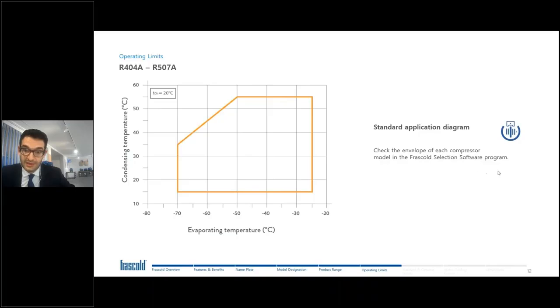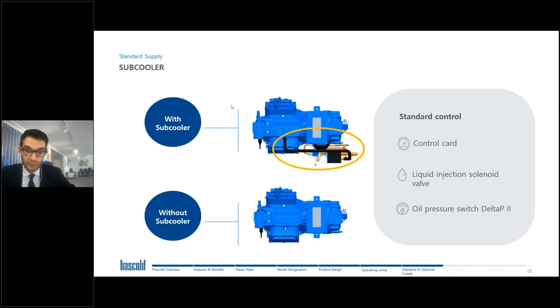Also, this envelope and all the performance in every point is available in the Frascold Selection Software. Here we can see the difference in a 3D drawing with subcooler or without. So we have two options. In our software, we give all the information needed to build the subcooler by yourself. Otherwise, we give you a subcooler with a filter, a solenoid valve, a sight glass, the expansion valve needed, and clearly the heat exchanger needed to make the subcooler, and this is already mounted by us.